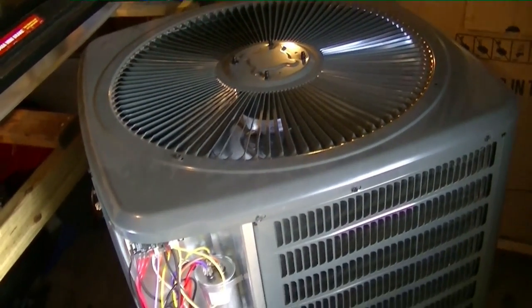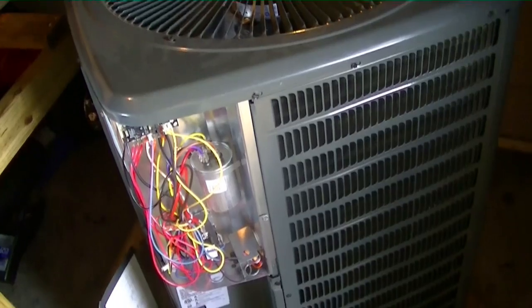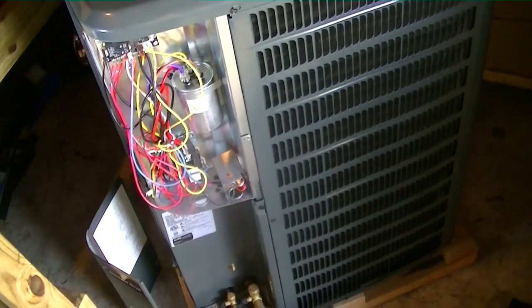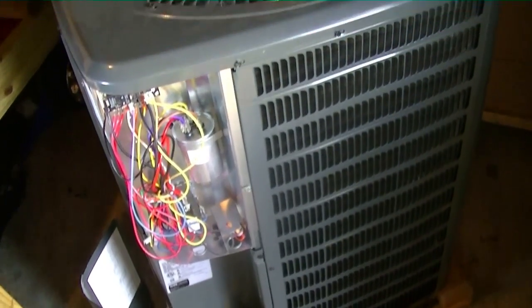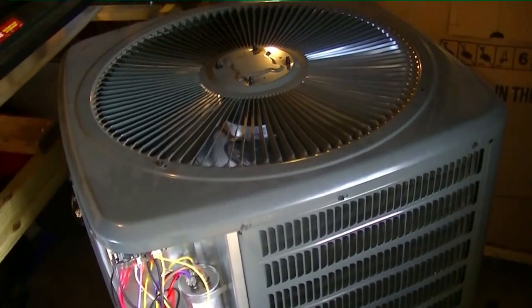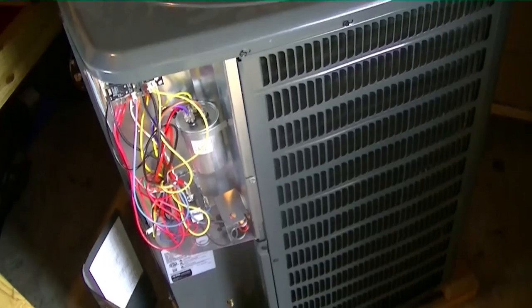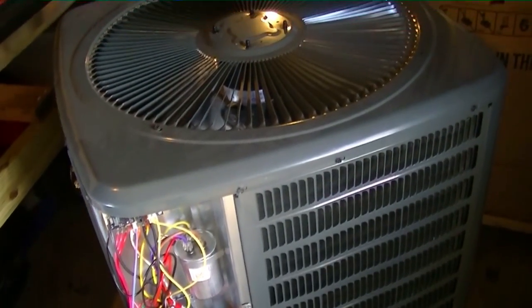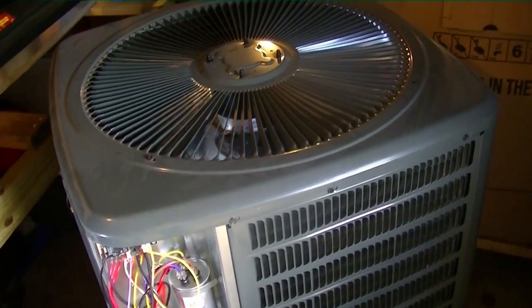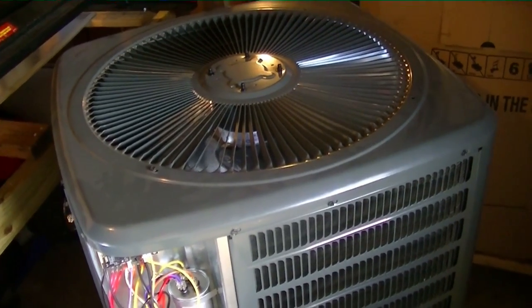That is a look at the dual run capacitor in a Goodman 14-seer heat pump. It serves the same purpose in many heat pumps. If you had an ECM fan motor, you would not have a capacitor for it, just like you wouldn't if it was a blower motor, but since these are both PSC motors, they use capacitors.